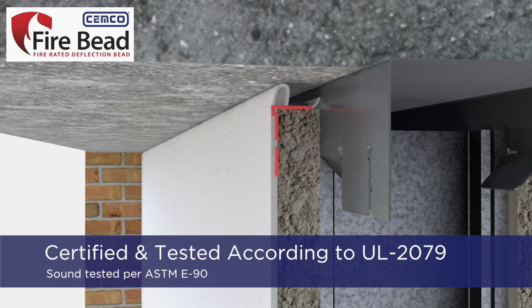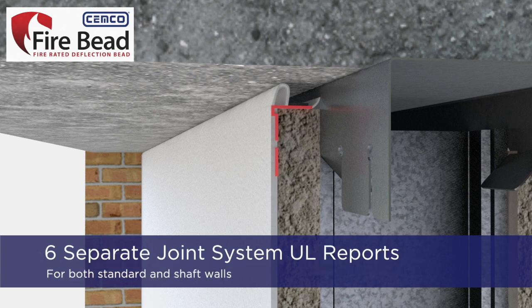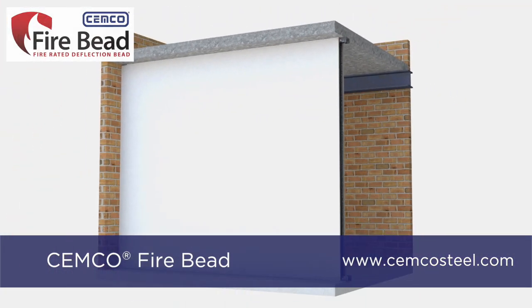The fire bead has been certified and tested according to UL 2079 5th edition and sound tested in accordance to ASTM E90. Fire Bead installations are not negatively affected by water or extreme temperatures. Fire Bead has six separate UL joint system reports for both standard walls and shaft walls and has an L rating of less than 1 CFM for 1 and 2 hour fire ratings. For more information, visit www.cemcosteel.com.